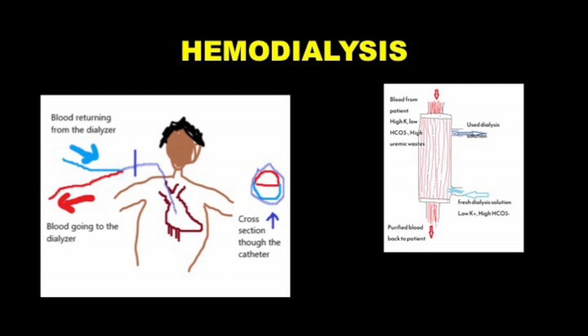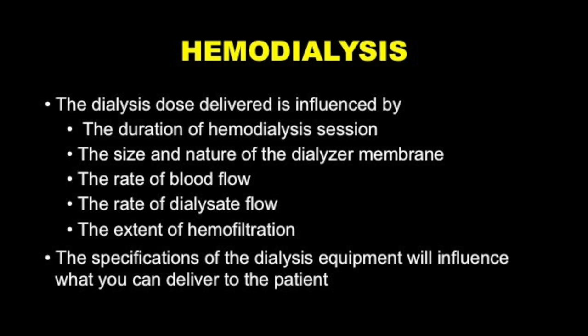At the end, you expect to achieve a more physiological balance after this process. You can decide how much exactly you want to do by varying the length of the session, the nature and size of the dialyzer membrane, the rate of blood flow delivered to the patient, the rate of dialysate flow, and whether you do additional things like hemofiltration, where you dilute the patient's blood and then drive it across the membrane faster than you would have without dilution.